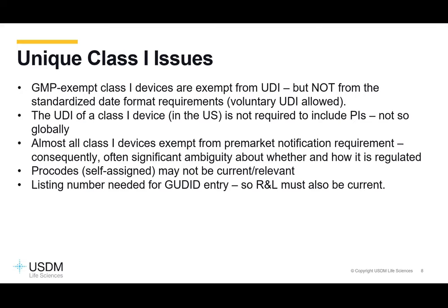I want to spend the last minute here really talking about the upcoming implementation in the US of UDI for Class 1 products. Very important time. This is what really brings value to the entire UDI conversation, is when we have UDI applied to all products, Class 1 being by far the largest group of devices that we're going to see. But there are a lot of unique challenges for all stakeholders when it comes time for Class 1 implementation, primarily because the vast majority of Class 1 devices are actually exempt from any sort of pre-market submission.